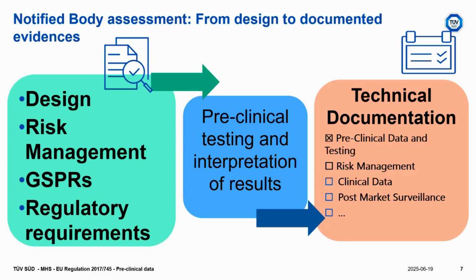And I think that what I'm describing here in the green square, design, risk management, GSPR, and regulatory requirement, is something that we also assess to check consistency and harmonization between each other. Just to give you an example, if we find a certain test and nowhere in the design plan, in the risk management, in the GSPR refers to the given test, we do not understand why you perform it. Or to justify certain acceptance criteria and decisions, we need that it is supported in any of the design documents, risk management, GSPR, or regulatory requirements.